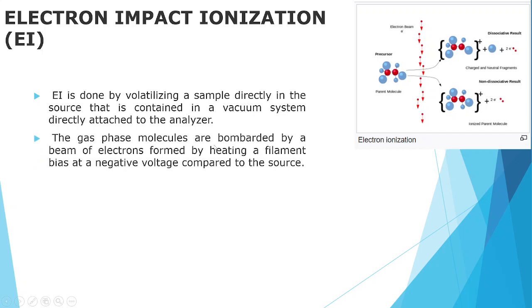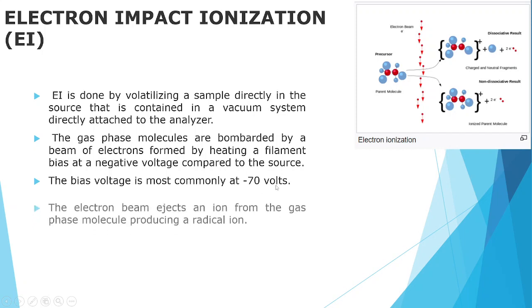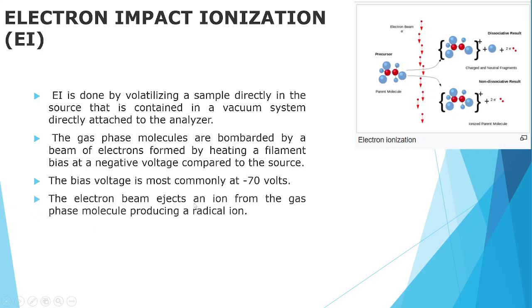The gas phase molecules are bombarded by a beam of electrons formed by heating a filament bias at a negative voltage compared to the source. The bias voltage is most commonly at minus 70 volts. The electron beam ejects an electron from the gas phase molecule producing a radical ion.